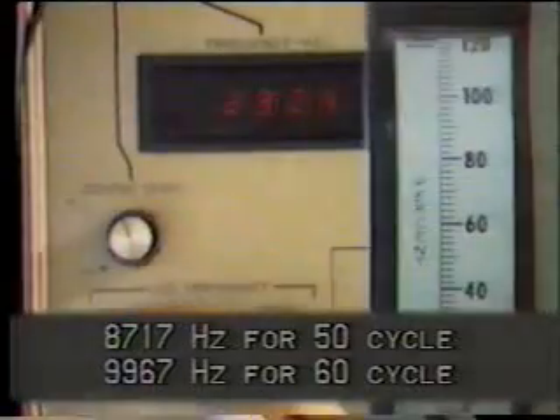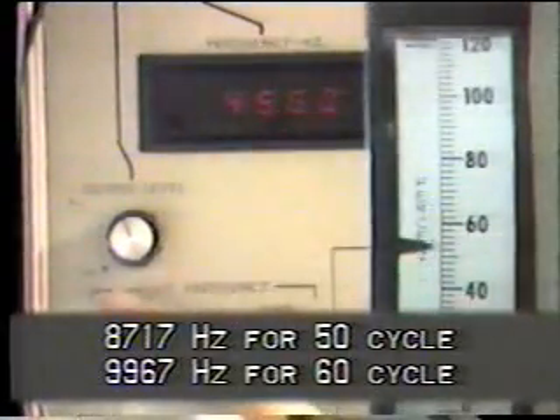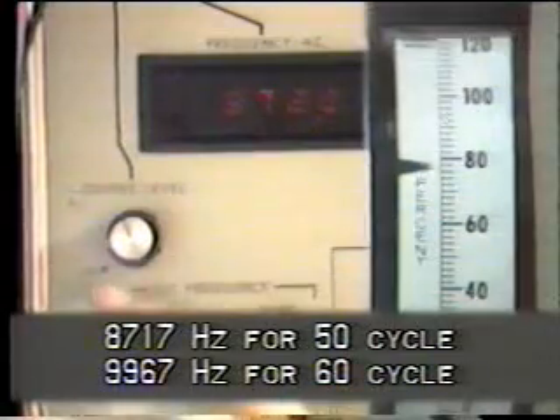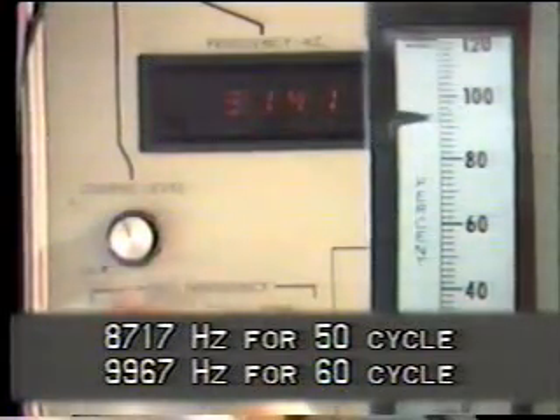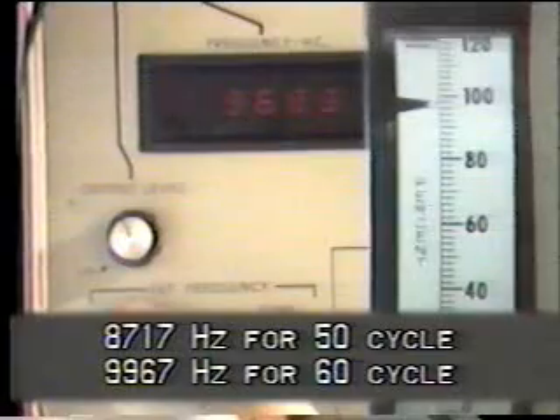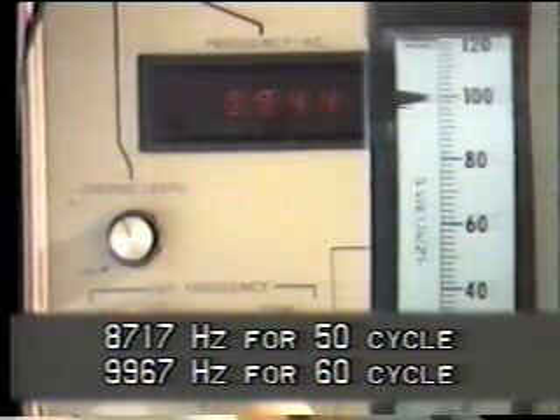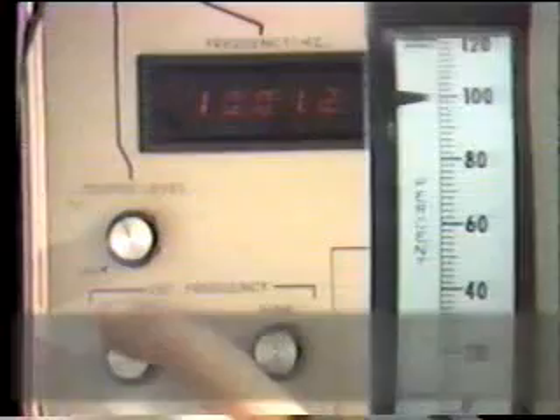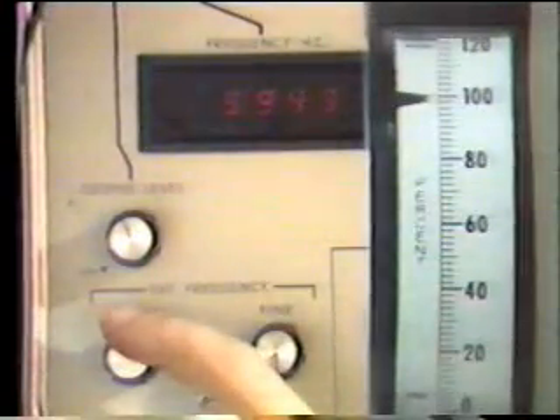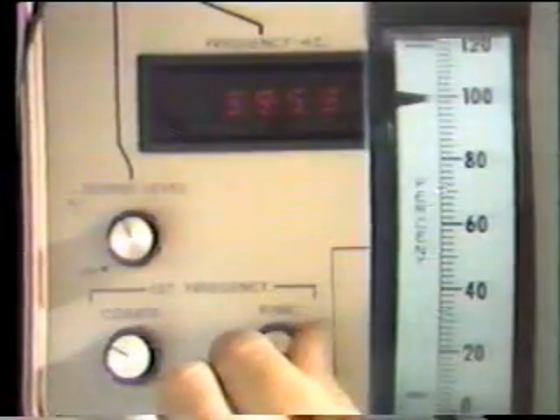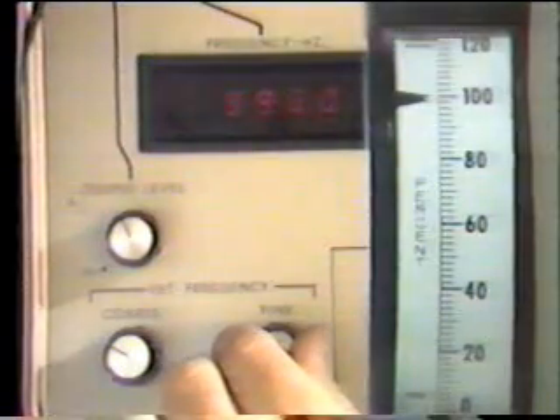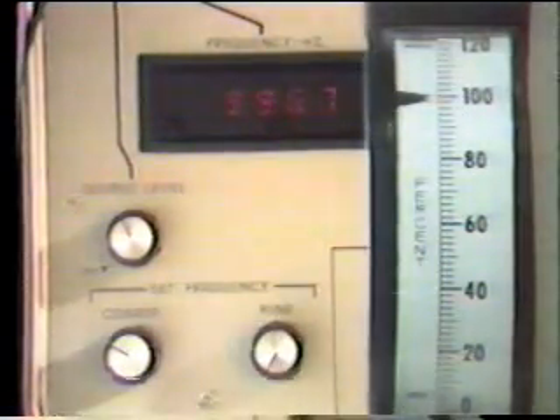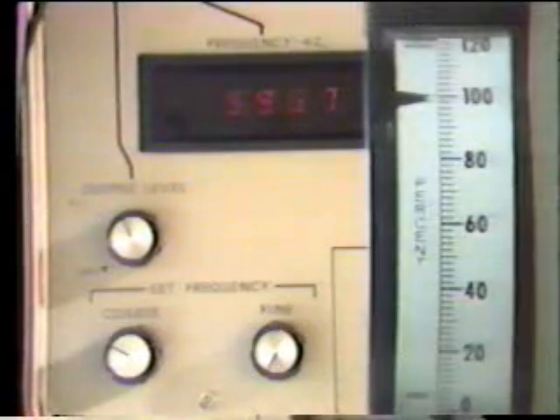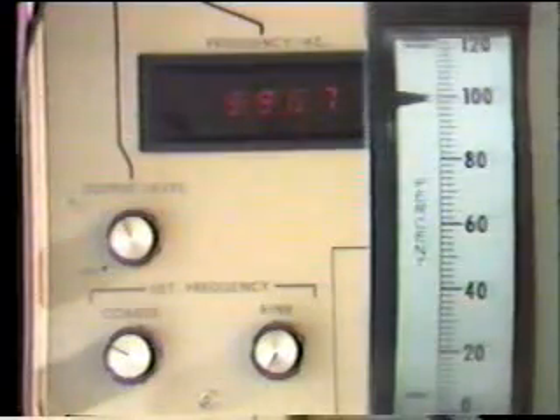First, adjust the frequency of the signal generator for 100% speed: 8,717 Hertz for 50 cycle generators and 9,967 Hertz for 60 cycle units. Remember, the voltage output should be 12 volts RMS nominal. While approaching 100% speed, notice that both the counter and speed meter represent visual displays of engine speed as simulated by the signal generator frequency. Check the speed meter. It should read 100% speed.